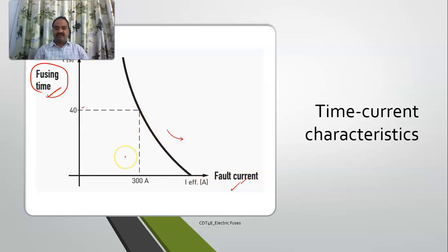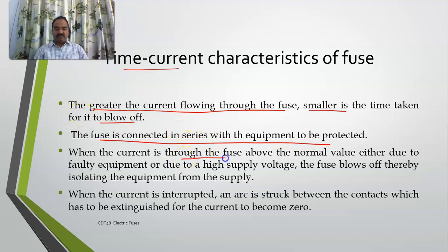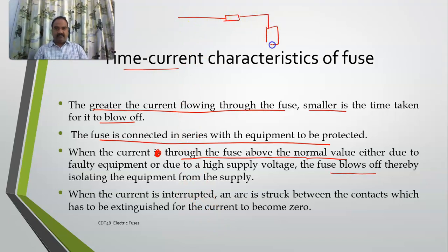The characteristic is inverse — that's why we call it the inverse time-current characteristic. For lower values of fault currents it may take some time, but for higher values it reacts immediately. For normal current, the time might be infinite, meaning it will not trip. The greater the current flowing through the fuse, the smaller the time taken. The fuse is always connected in series with the equipment, so when current exceeds normal — due to faulty equipment or a sudden voltage surge — the fuse blows off, isolating the equipment.